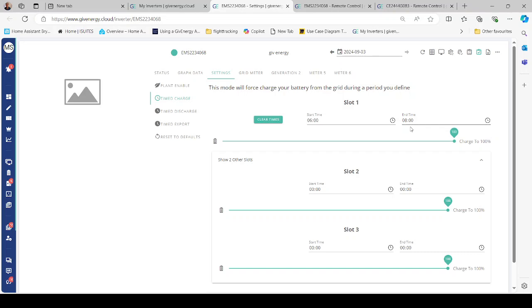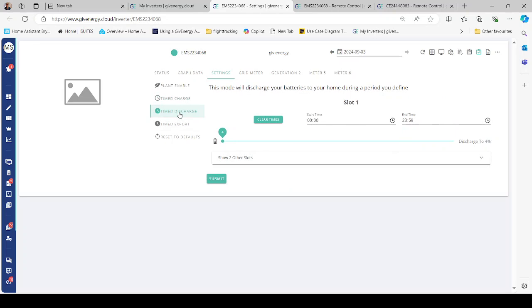Now, if it was something like Intelligent Octopus, you would have from 0000 to 0530, and then you would have the evening slot of 2330 to 2359 as slot 2. And you would put in there what you would want it to charge up to. If you look at timed discharge, that is the eco mode for the EMS. If timed discharge is set, it will try and support the house load using PV first, battery second to supplement PV, and if that's not enough energy, then allow grid as well. And you notice here that we have a start time of 0000 to 2359, so we have eco set for all day long. Timed charge will take priority over that, and will charge in the time slots presented.